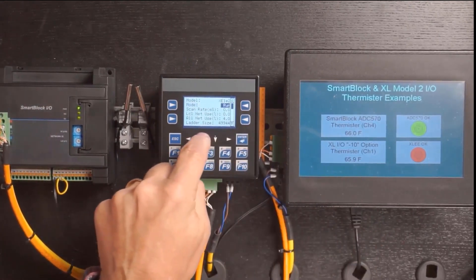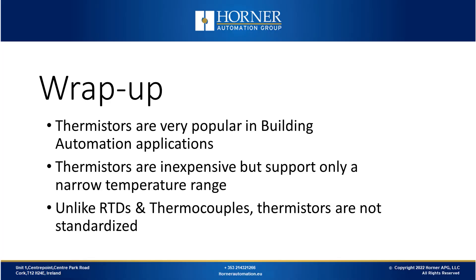So that is a look at how to apply thermistors with the Horner OCS. The important points today are that thermistors are extremely popular in building automation applications and are very inexpensive. They only support a narrow temperature range, but for HVAC and building automation that's not a problem. Unlike RTDs and thermocouples, thermistors are not standardized, so be careful in terms of which thermistors you source. If using them with a Horner controller, choose from the Kiel or the YSI — they are widely available, very inexpensive, and they'll work extremely well with the Horner controllers.